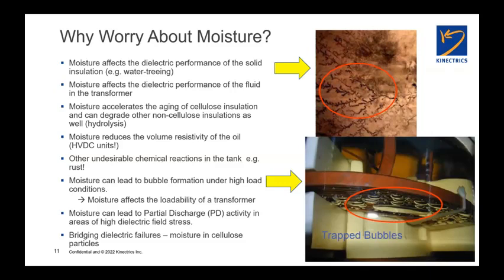Again, maybe something that's not obvious, but very detrimental to transformers is it can affect the loadability of the transformer. You can imagine if we've got moisture in the paper insulation, as the transformer is increasingly loaded, the load increases, the windings get hotter. And 80, 90, 100 degrees C is not an unusual temperature for a fully loaded power transformer in the windings. And guess what? At 100 degrees C, what happens to any moisture that's in the paper? It boils and it turns to steam, and the steam comes out as bubbles. And bubbles are very bad for obvious reasons.